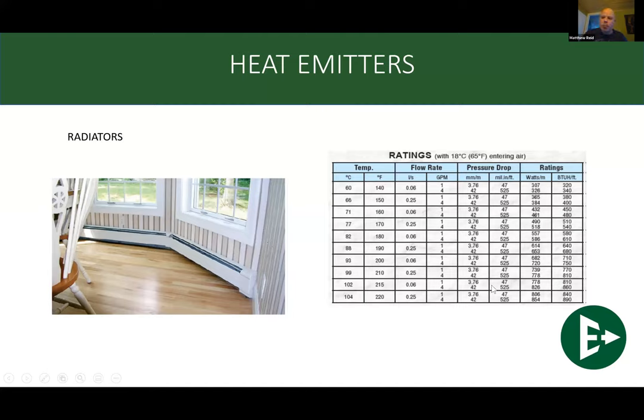So if I wanted 600 BTUs, I go over here to my BTU chart and I don't cross into 600 BTUs till I get down here. So I know that in order to get 600 BTUs, I've got to be moving 4 GPM at 180 degree temperature per foot. Or I could divide that in half and go down and use a 300 BTU per foot of baseboard heating. I can still get my 600 BTUs, I just need to increase the length of the baseboard that we're going to be going over. So that's how we size the radiator per room.